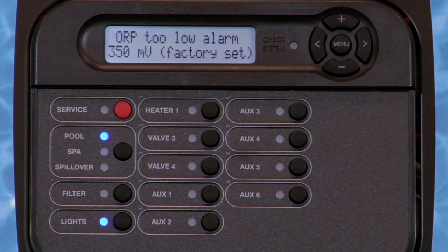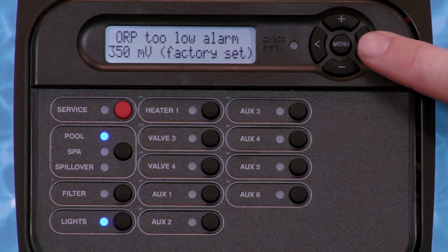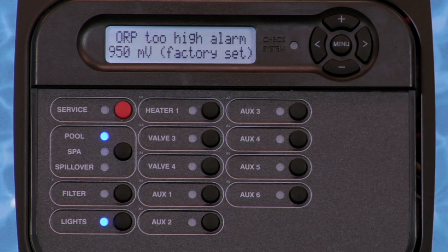Press the right arrow key twice to move through the next two screens, which display the ORP too low alarm and ORP too high alarm levels. These alarms are similar to the pH alarms discussed earlier. Both types are factory set and cannot be adjusted. Should the ORP level in the water drop below 350 millivolts, ORP low, or rise above 950 millivolts, ORP high, the ProLogic will display an error code to alert you.